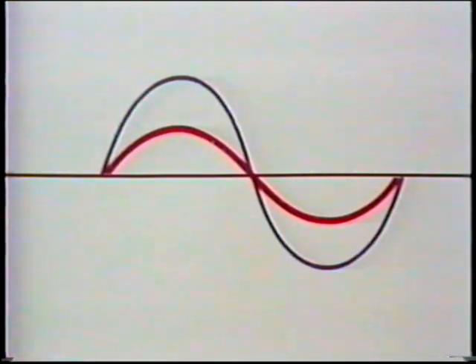Overexciting or underexciting the rotor windings causes current and voltage in the stator to go out of phase with each other. This causes current flow in the stator to increase. The motor uses more current to produce the same amount of work, so the electrical efficiency of the motor decreases. If we look at the sine curves of voltage and current in the stator of a synchronous motor, we can see how the rotor field affects their relationship. These sine curves show the relationship between current and voltage in the stator when the motor operates at maximum efficiency. Notice that current and voltage are in phase with each other.